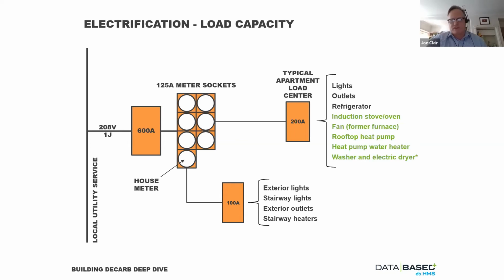Depending on what services are in an apartment, maybe there's no central washer and dryer, or you can find a way to make the HVAC a separate service. There are some ways around this, but in a lot of cases you're going to need to upgrade that load center, and maybe even the main service to the building. This can be a bit of a challenge, and this is where the idea of planning out and identifying when to make that upgrade comes in. You can probably swap out or add one device into the existing load center, but you'd have to upgrade it if more were needed. So that goes into the planning piece of it.